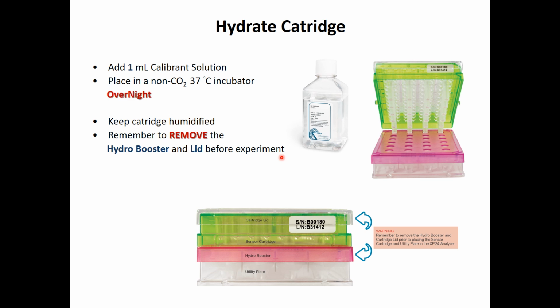If you want to keep it out in the environment for a very long time, we will just use something easy to cover the light. As you add the calibrant solution to each well, please put it in a 37-degree incubator, but no CO2. Remember, non-CO2, and keep it overnight. Because the calibrant buffer is already adjusted to pH 7.4, if you have any CO2 or excess CO2 in the incubator, then your pH level will decrease, so the calibration result will be wrong.